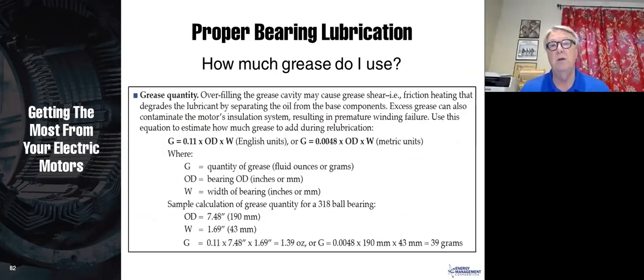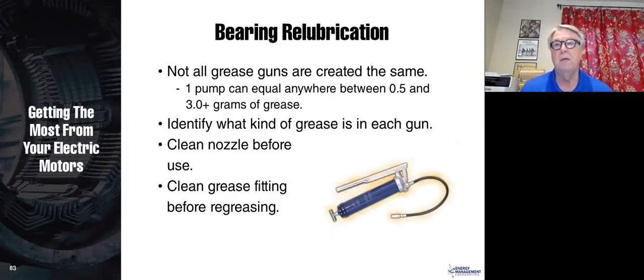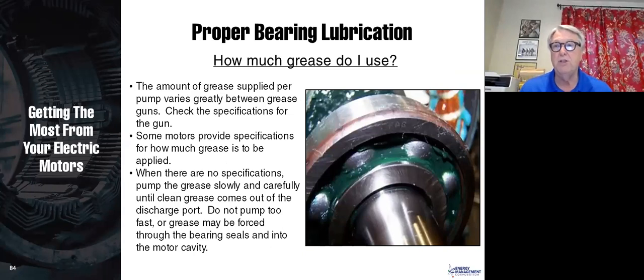How much grease do you use? Well, this is a formula, and if you want to look at the bearing diameter and so on, you can use this, but typically people don't do this. Most people who grease motors don't like to sit and do formulas. So mostly we just pump it until clean grease comes out. Remember that not all grease guns have the same amount of grease per pump. Now, how much grease should you use? Well, again, I showed you that formula, but the best way to know that is on the motor data sheet. The next best way is to just wait till the clean grease comes out.